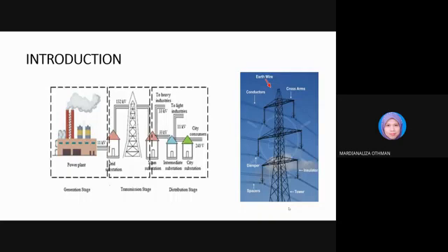For the introduction, electricity produced by a generator in a power plant is transmitted over a long distance to consumers through the transmission line. The overhead line is kept in the middle of the air and connected to the transmission tower to provide the necessary minimum ground clearance based on the overhead line voltage level. The overhead conductor must be electrically disconnected from the ground potential of the transmission tower. The equipment that performs the dual task mentioned is known as a transmission line insulator, or simply an insulator.